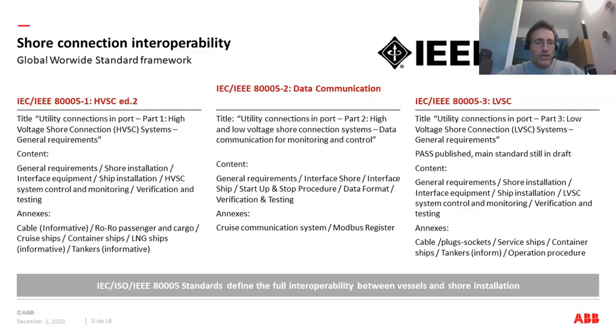Different types of vessels require different amounts of power, and to some extent different voltages. There is a standardized low voltage shore connection that can fit vessels with 400, 440, or 690 volts. Here we're facing vessels with consumption around 1 to a few MW, and frequency that can be both 60 and 50 Hz.